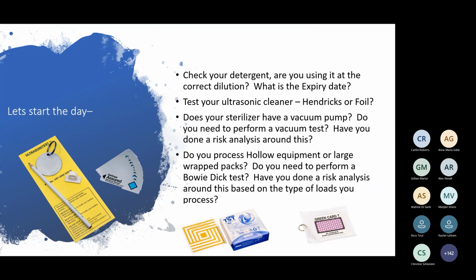Does your sterilizer have a vacuum pump? Do you need to perform a vacuum test? Have you done a risk analysis around doing a vacuum test on your machine? How often do you need to do a vacuum test on your machine? And why are you doing a vacuum test on your machine? Do you process hollow equipment or large wrapped pack? Do you need to perform a Bowie-Dick test? Have you done a risk analysis around this based on the type of loads you process? Now, these 2 things are probably some of the sticky questions that I get asked a lot.